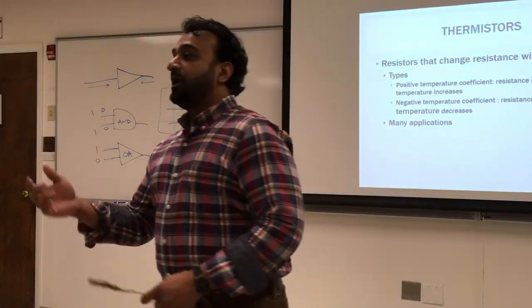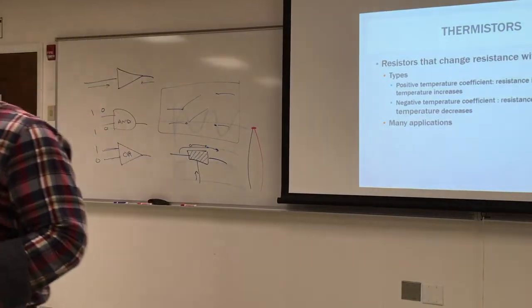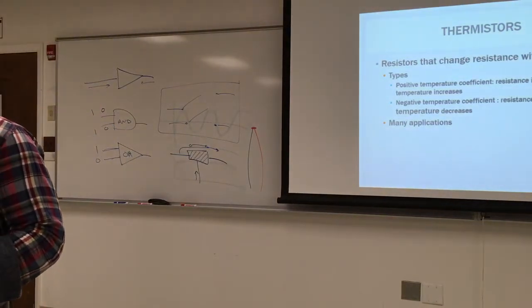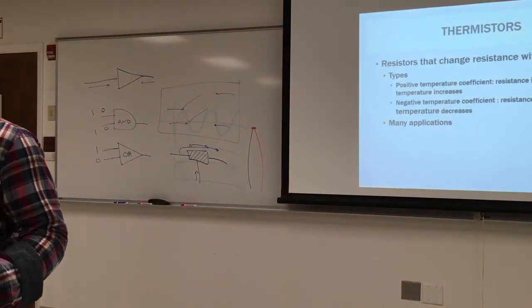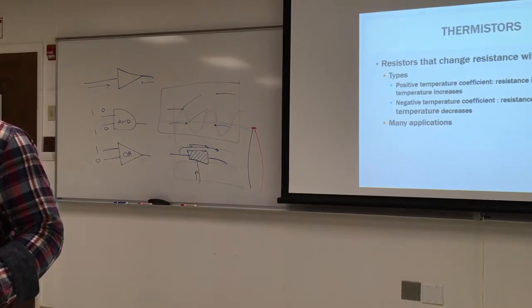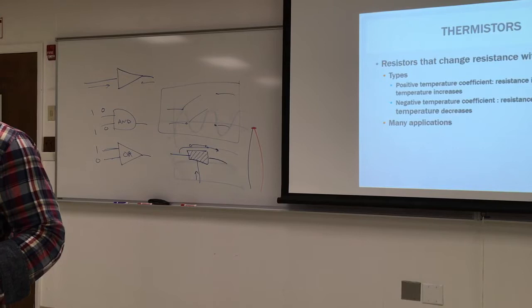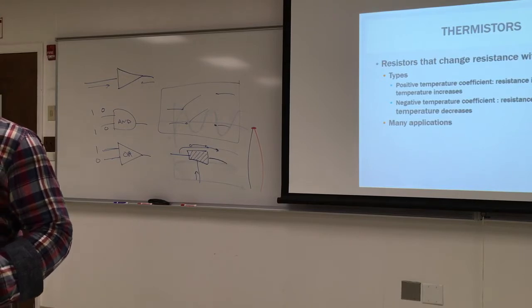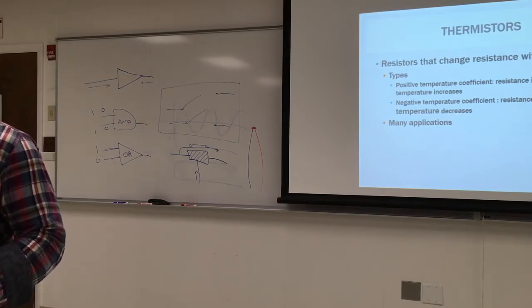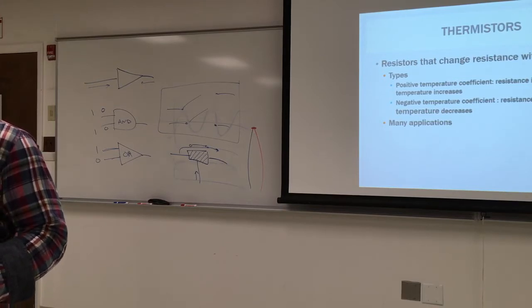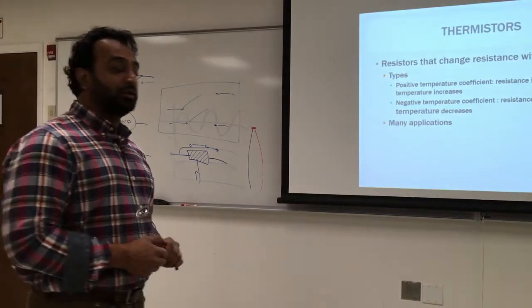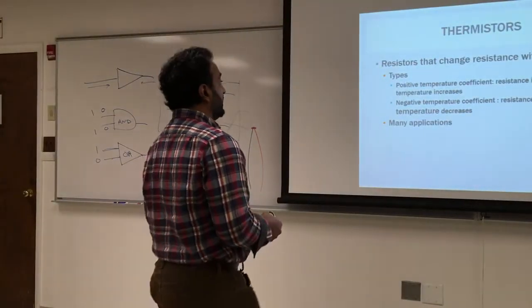Another question we need to know is what accuracy we need from that sensor. Some of them have to be very, very accurate, within half a degree, 0.1 of a degree. It's not going to be that accurate in our field, but we do want something within 5 degrees accuracy at least, even in HVAC. That's a little bit too sketchy, 5 degrees is too much. So you want something within like 1 degree, half a degree.